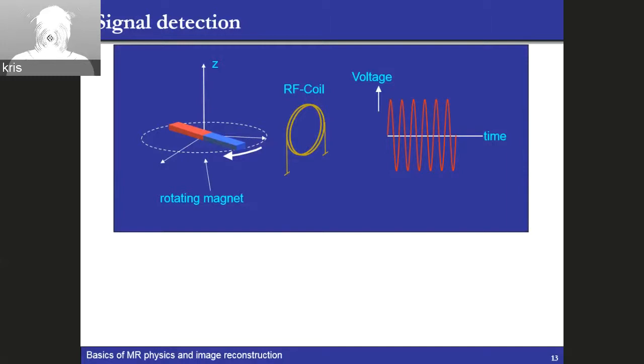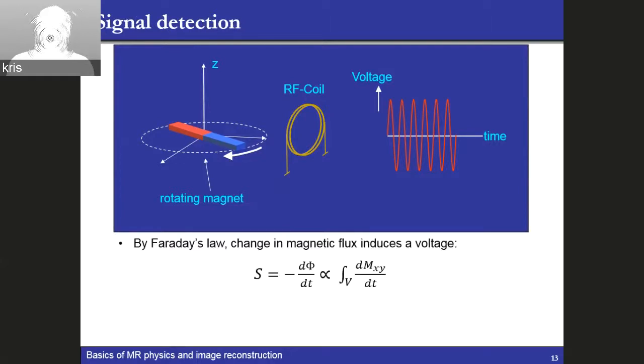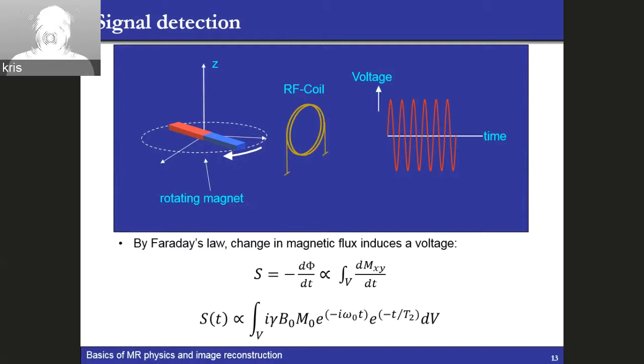We now have a signal generated in the transverse plane, scaled by some constants. To measure the signal, we rely on Faraday's law — as the magnetization changes, it introduces a magnetic flux which can induce a voltage in a nearby coil. The change in flux will be proportional to how the magnetization evolves over time. The signal — this induced voltage — is proportional to the gyromagnetic ratio, the B0 field, and also to M0. Since M0 is also proportional to B0, there is a heavy dependence on the field, which is why there has always been a drive to go to higher fields in MR for higher signal.